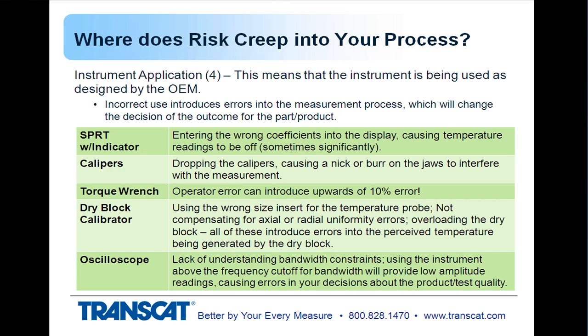An oscilloscope, for example, if you're using it above or near its bandwidth limits, can cause a frequency cutoff for the amplitude, and you get a different reading than you think you're getting. And again, you're making decisions based on that for your product or your test of your product, and that can change everything about whether you call that good or bad.